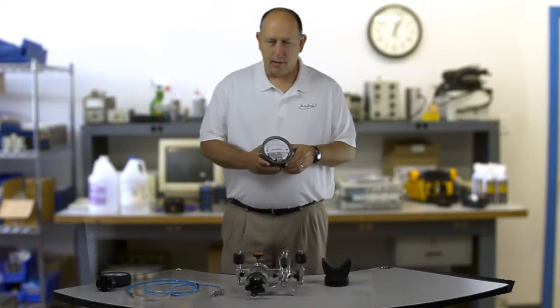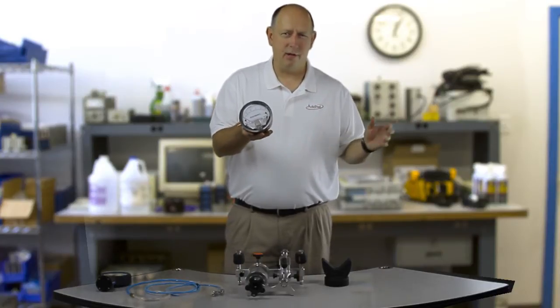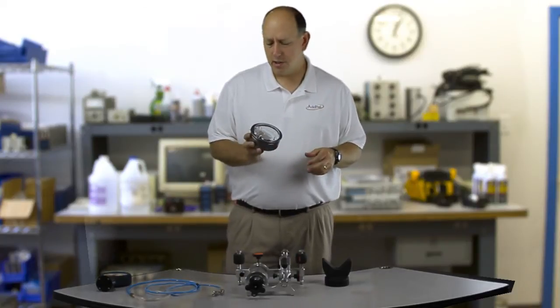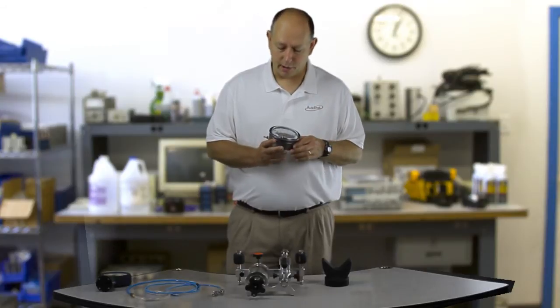What I want to talk about today is magnehelic pressure gauges — differential pressure gauges. There are literally tens of thousands of these out there in industry. They're low pressure differential gauges and they're very difficult to calibrate because of the extreme low pressure that you're working at.